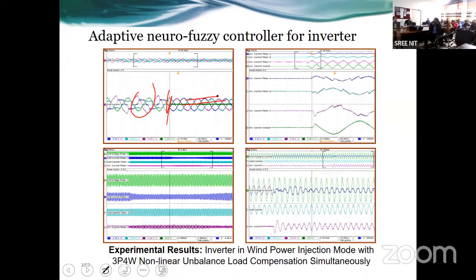For 3-phase unbalanced load, we have several mitigation techniques to balance it. We don't need an inverter also. We can balance it directly using capacitor and inductor. But that is not active, no? That is not active power. This is a passive element, no? Or they will do it in steps. Here it is perfectly balanced, and the converter itself is being utilized. No additional device is being introduced. It is the same inverter which is there to evacuate the power.